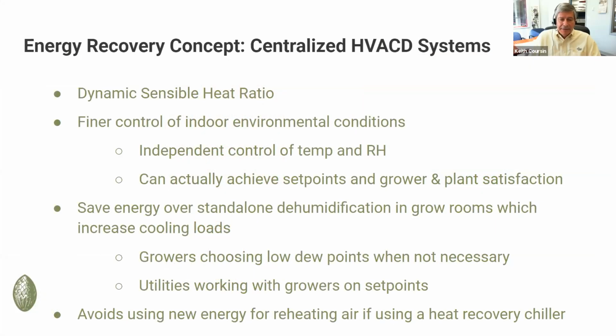Yeah, the dehumidification impact of using that heating energy, as I mentioned at the onset, is about temperature and humidity, and you have to have control over both. As plants grow in size, their transpiration rates change, so the actual dehumidification load is changing, and as the dehumidification load changes, the sensible lighting load changes. So you have this dynamic, from the small plant to the large plant, that is going to change every single day of that growth cycle.